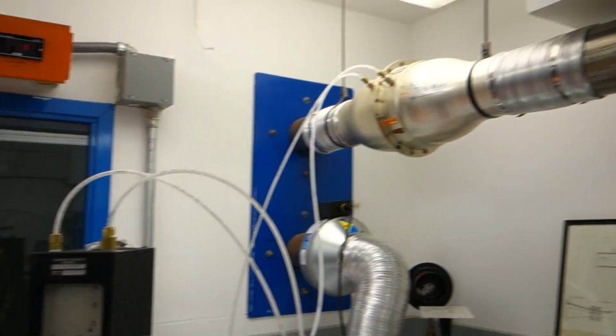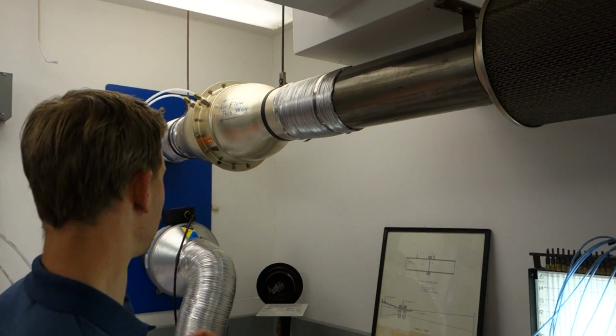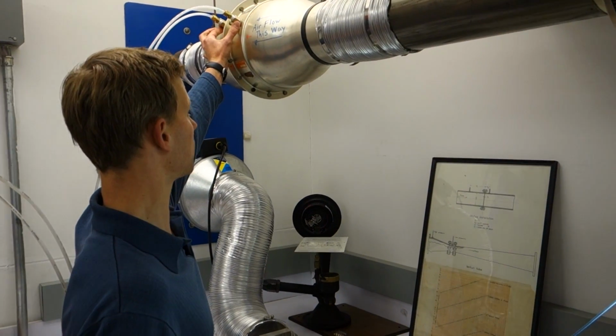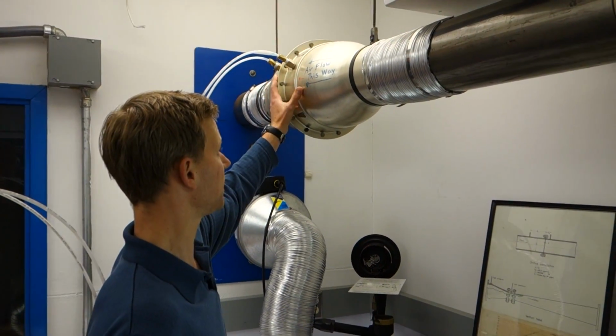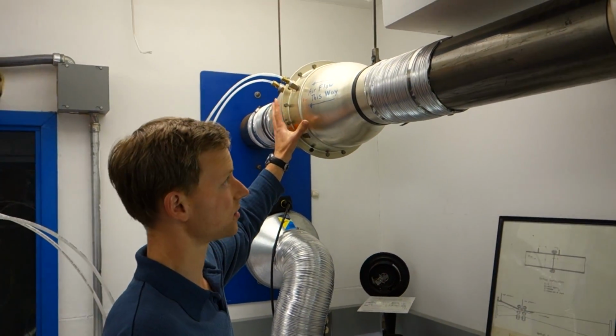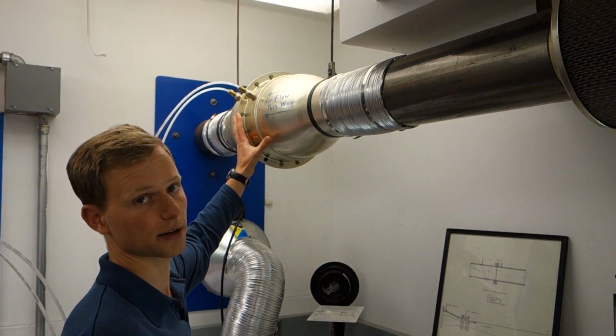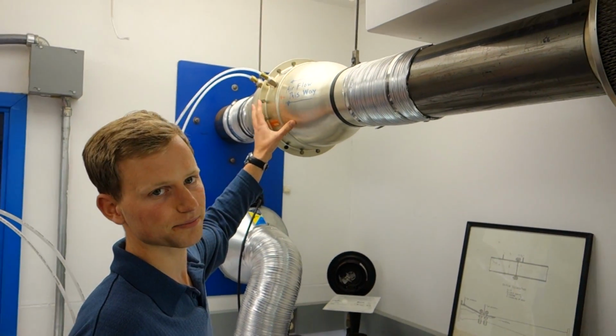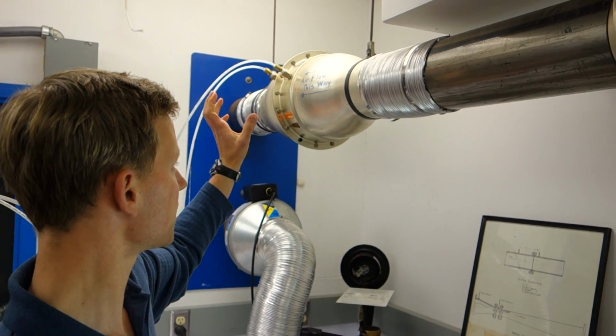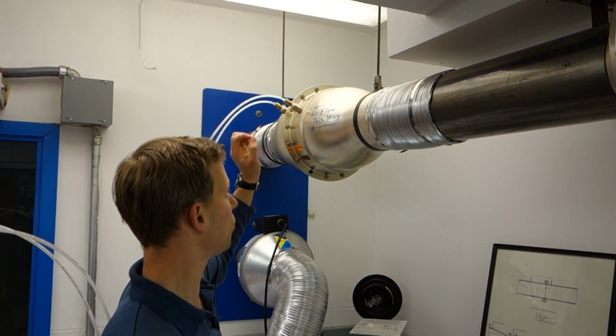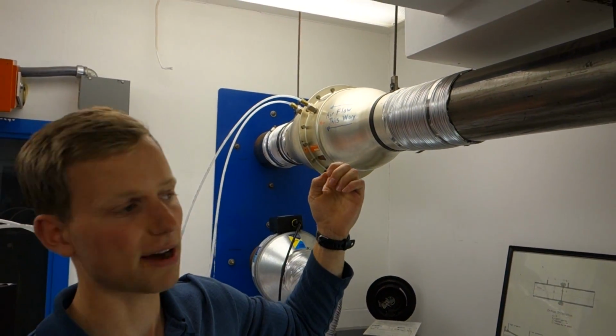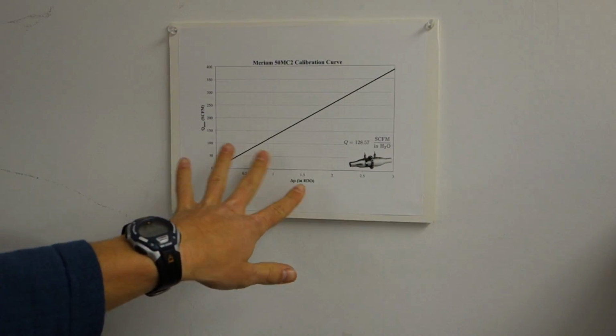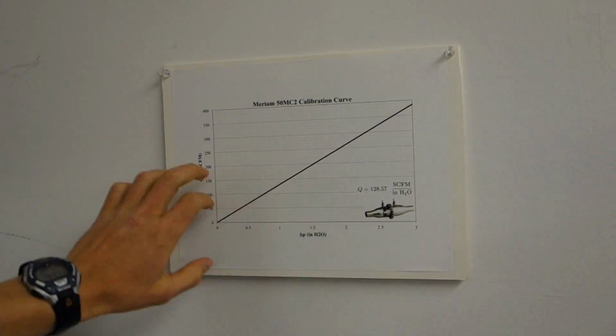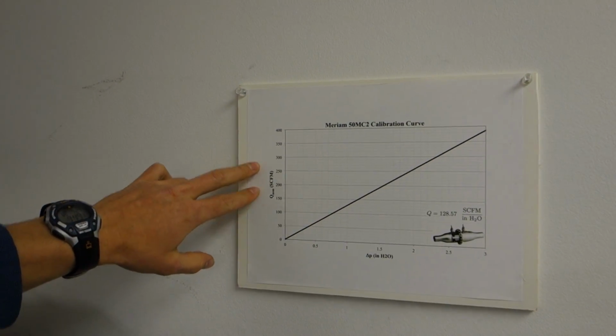The other part of the station is we will measure the pressure drop across the laminar flow element. Now this thing, you can go online and buy. It's installed in your system to measure flow rate. And we have a calibration curve: given a delta P, what will be the flow rate? We have that on the wall over here, which is a linear relationship between delta P in inches of water and Q in standard cubic feet per minute. Okay, so with that, we'll turn on the system.